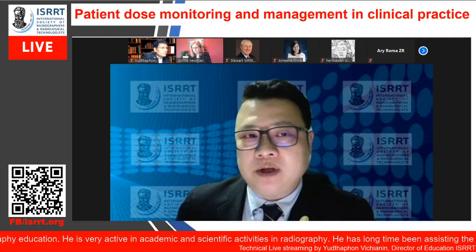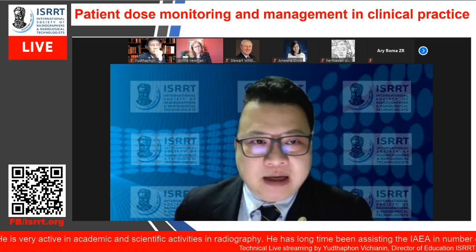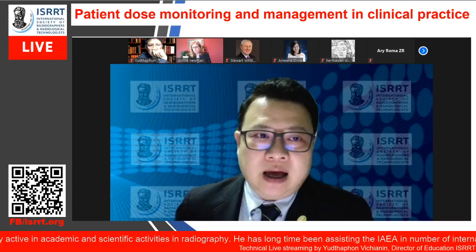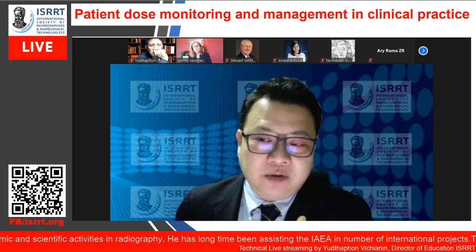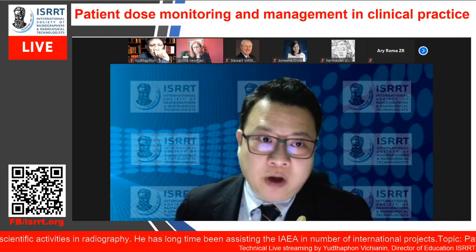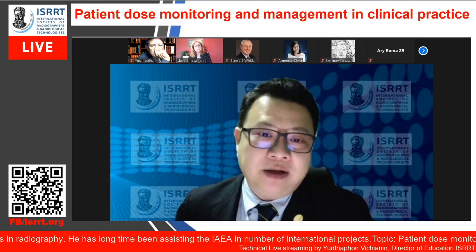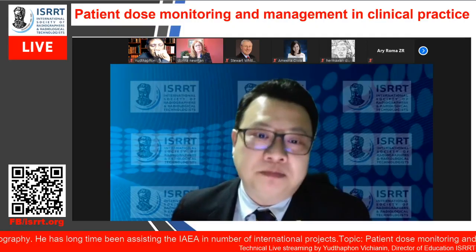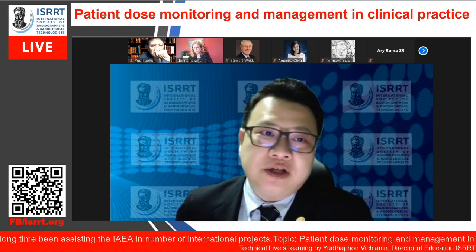Say in one hospital, you have this protocol coverage, and then a kVp of this, this collimation, this pitch, and so on, this mA. That's going to influence the CTDI volume. Once you change the parameter and then you want to compare the image quality, then you compare the CTDI volume. That's for technical comparison, not the patient dose.